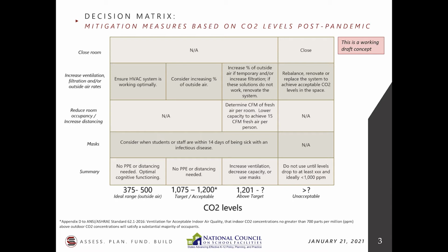Yeah, I mean, carbon dioxide, we all use it. But it's a crude surrogate, if you will, for outdoor air provision to a classroom. I say crude in that there are many advantages, in that it's simple to do, but behind all of that there are quite a few assumptions that have to be met to be more accurate in what you're reporting and what those levels actually mean. What I mean by that is you have to assume that you've got good calibration.